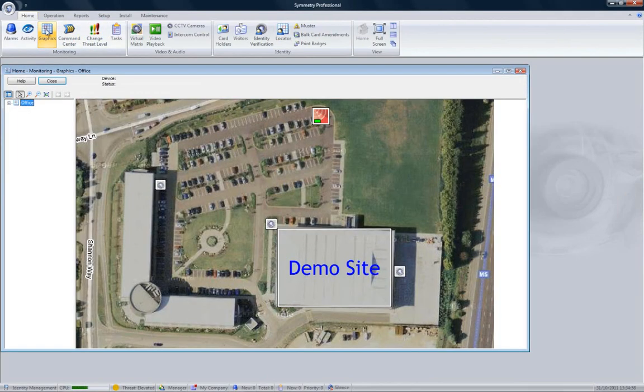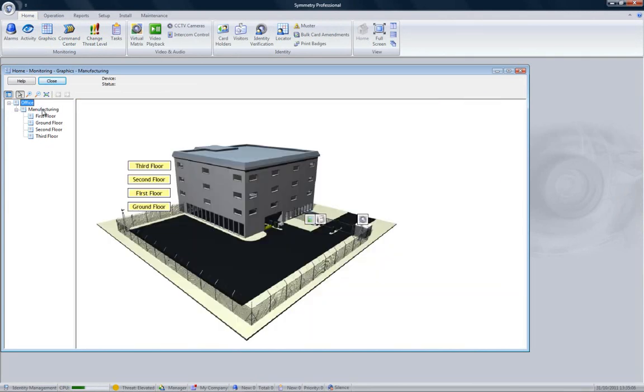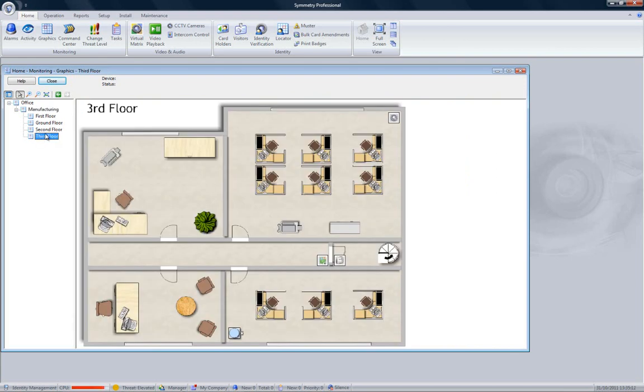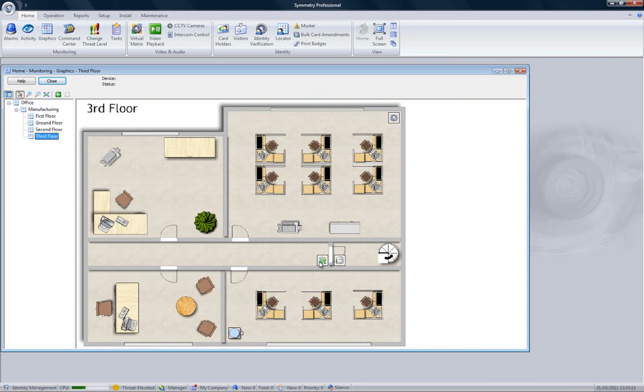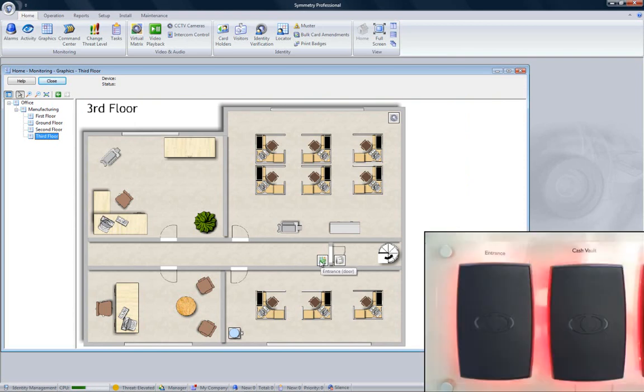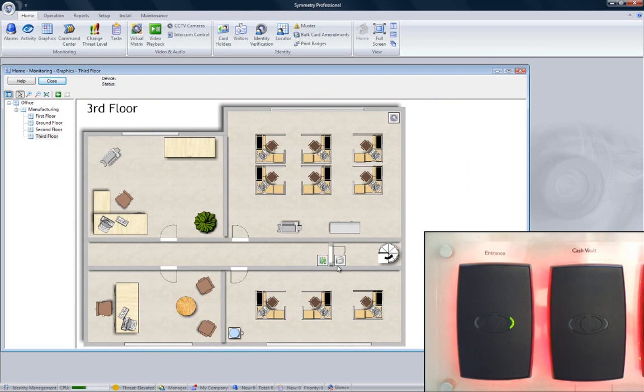The graphics screen can be really useful, as it provides a simpler user interface to allow an operator to see what's actually happening on the security system. Here we can see the layout of two buildings. If we had an alarm in the log, we would see a red box around the appropriate part of the image. We can select more levels to give more detail, until eventually we can see the graphics screen also allows control of devices. If we right-click an icon for a reader, we can select Grant Access, and we see the green LED coming on, showing that the door has been released.